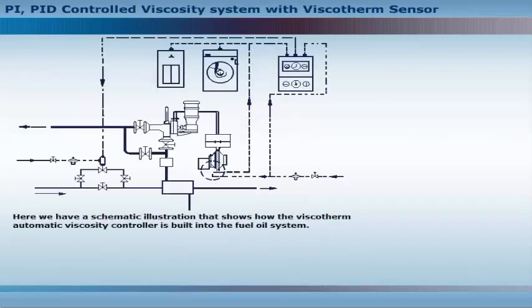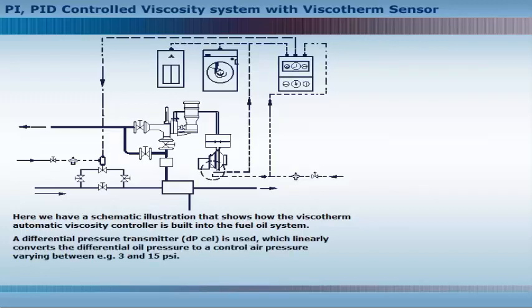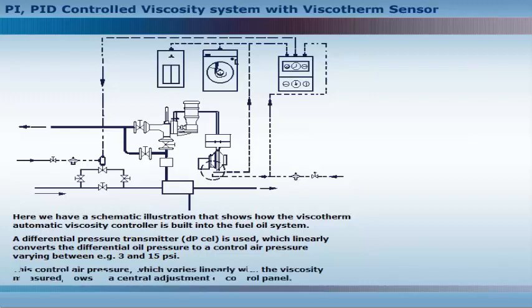Here we have a schematic illustration that shows how the viscotherm automatic viscosity controller is built into the fuel oil system. A differential pressure transmitter is used, which linearly converts the differential oil pressure to a control air pressure varying between 3 and 15 psi. This controller air pressure, which varies linearly with the viscosity measured, flows to a central adjustment or control panel.